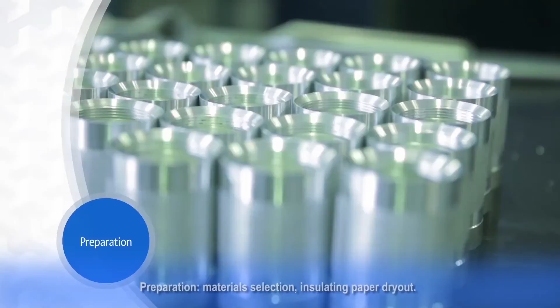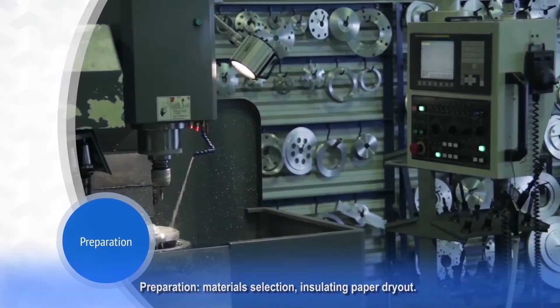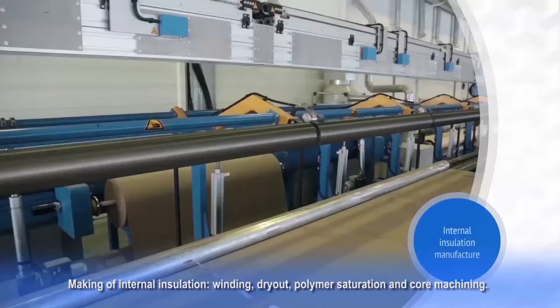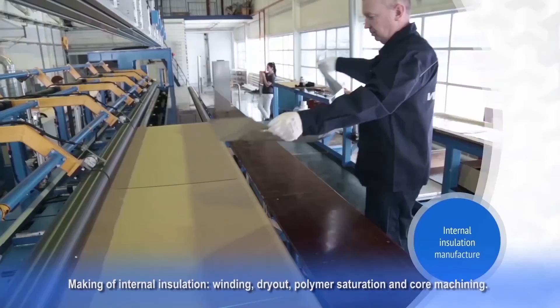At the preparation stage, all necessary materials and completing parts are selected, smaller operations are made with minor parts, and insulating paper is dried. The next step is manufacture of internal insulation of bushings, when winding of the insulator core is done with condenser plates used to level the electric field.